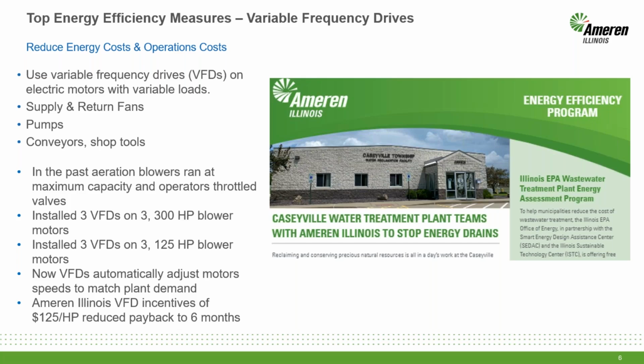This year, the Caseyville Township Water Reclamation Facility worked with the Illinois Environmental Protection Agency's Wastewater Treatment Plant Energy Assessment Program. A free assessment was provided, and Caseyville used the recommendations to guide them. This year, Caseyville installed 6 variable frequency drives to adjust the aeration blowers to match the varying plant demands. The drives were installed on 3 300 horsepower blowers and 3 125 horsepower blowers, leading to significant energy savings.